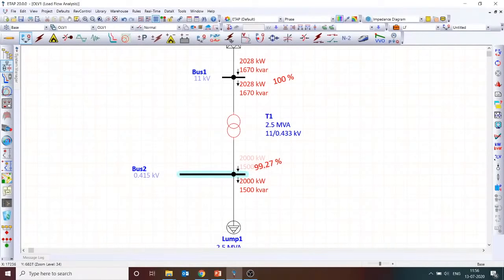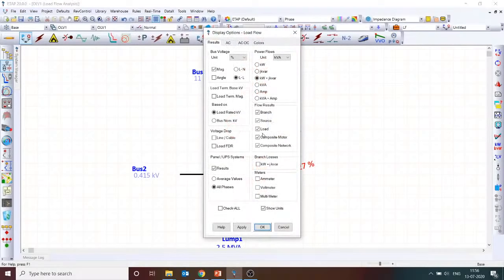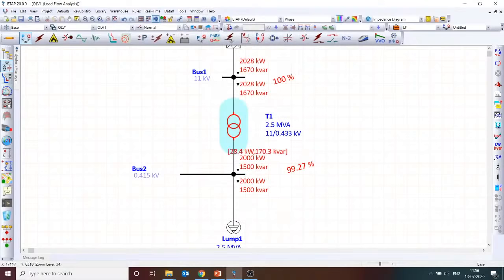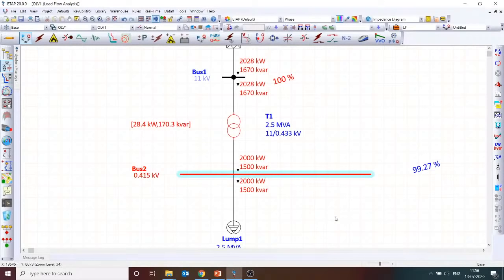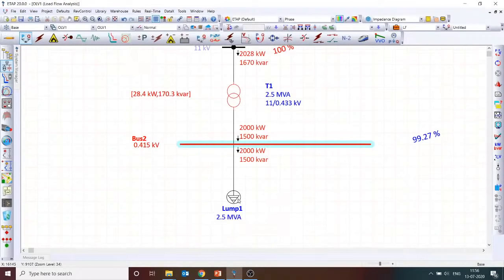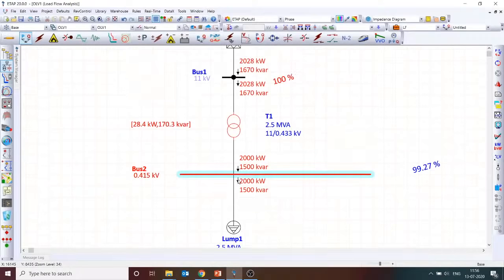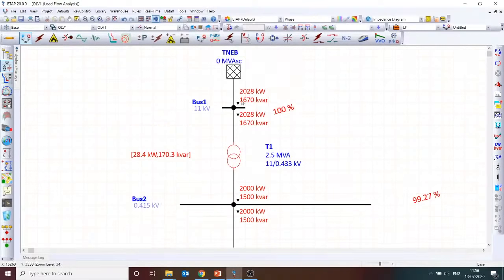Let me reduce it. So here you can understand two or three important observations. I can plot the losses of the transformer as well. Previously I ran this industry without any load. Now I am running it with the complete 2.5 MVA load. From this, you can understand the transformer is already overloaded. That's the real reason why the transformer is in red color. All other equipment is not in red color, but the transformer is.